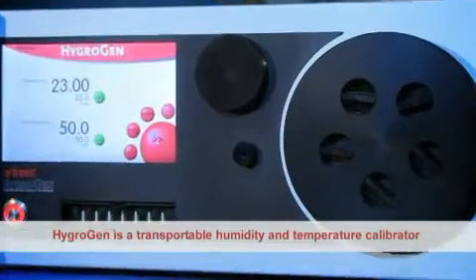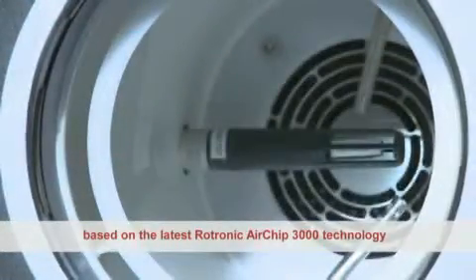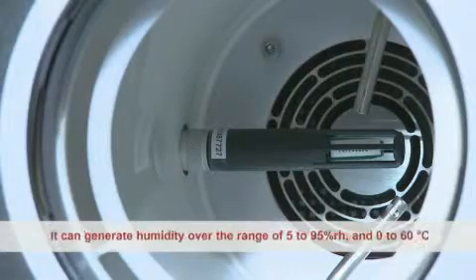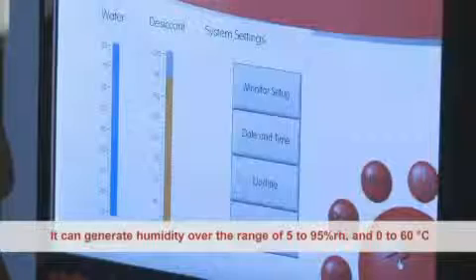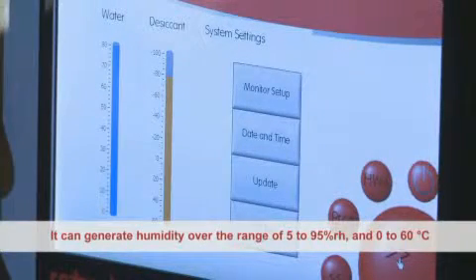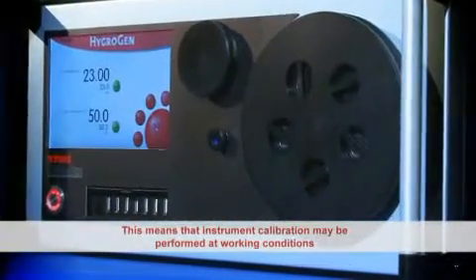HygroGen is a transportable humidity and temperature calibrator based on the latest Rotronic AirChip 3000 technology. It can generate humidity over the range of 5-95% RH and 0-60 degrees C temperature. This means that instrument calibration may be performed at working conditions.